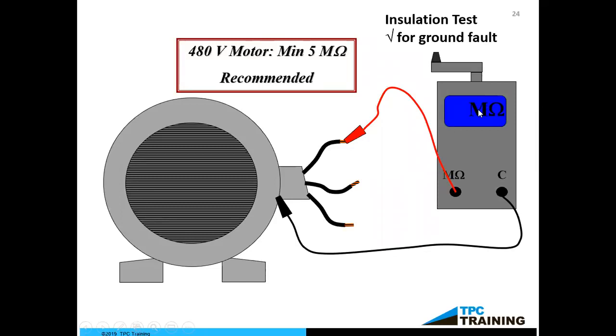But with a digital megger, you just have to press a button, and then the meter will cycle through and give us a number. And the National Electrical Testing Association recommends that we have at least 5 megohms. If you ever get down near 1 megohm, then that motor's not going to start. It's hopefully going to trip a breaker or open up a fuse, so we don't cause any damage to personnel or equipment. But we're really looking at 5 megohms as the minimum number to determine here.